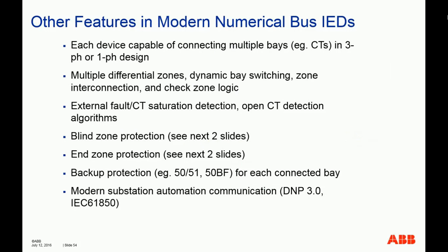Okay, other features in modern numerical bus IEDs. In modern numerical bus relays, each device is nowadays capable of connecting multiple bays, just like the high impedance relays. Nowadays, each box, each bus protection relay, we call it a box. Most of them support at least 6. You can connect 6 three-phase CTs to it. Some can connect 8 CTs and protect those 8 bays. Or you can opt for the single phase design. Single phase design means 3 boxes, because bus differential protections are phase segregated. Each phase makes independent decisions, so it doesn't matter whether they are located in the same box or separate boxes.